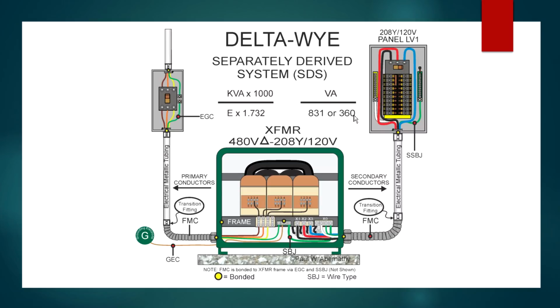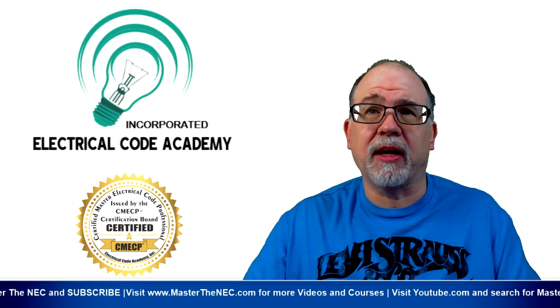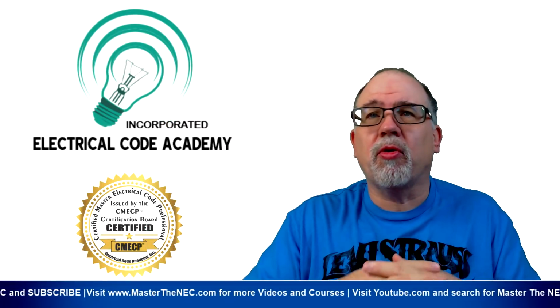Now again, if we use our calculator, and I'll just keep it on the presentation, you can just do it yourself. But if I take the 208 times 1.732, that gives me 360.256. Well, I can just use the 360, and that will be fine. Okay? And we're going to calculate that out all in a minute. But there's one more that I don't show on the screen.